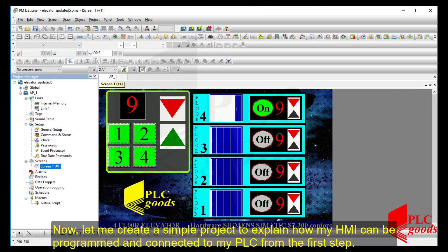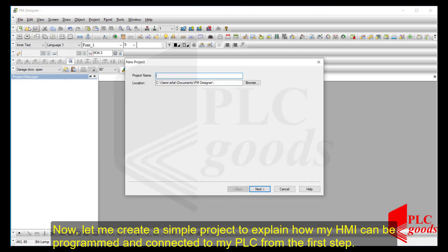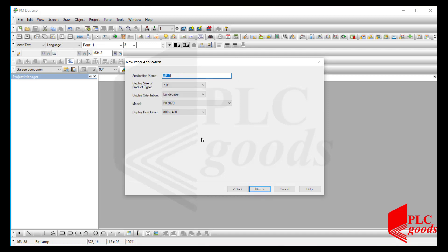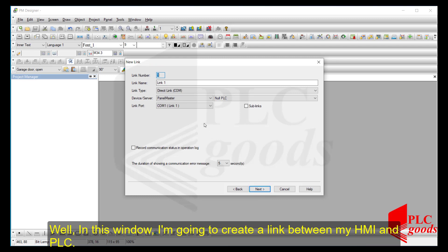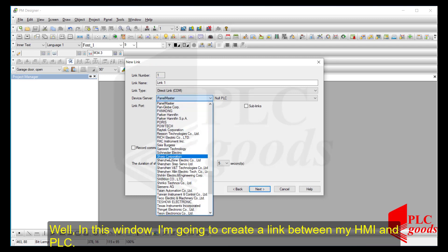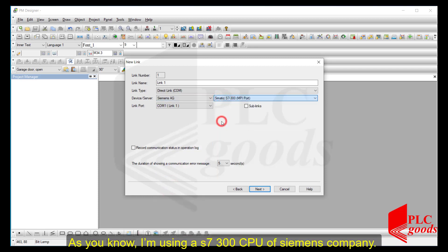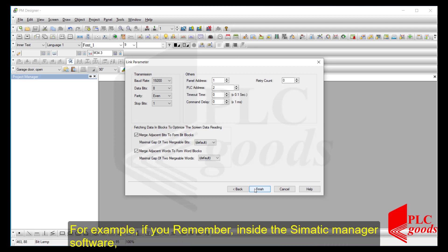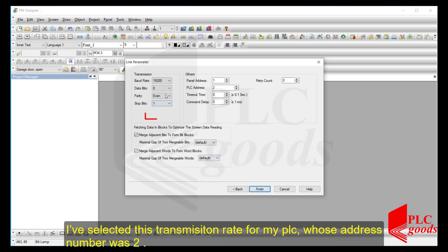Now let me create a simple project to explain how my HMI can be programmed and connected to my PLC from the first step. I need to write a name for my new project, and after that I'll determine my HMI model. In this window I'm going to create a link between my HMI and PLC. As you know, I'm using an S7-300 CPU from Siemens. Now I can modify the created link's parameters — for example, the transmission rate I selected inside SIMATIC Manager, and my PLC address number is 2.